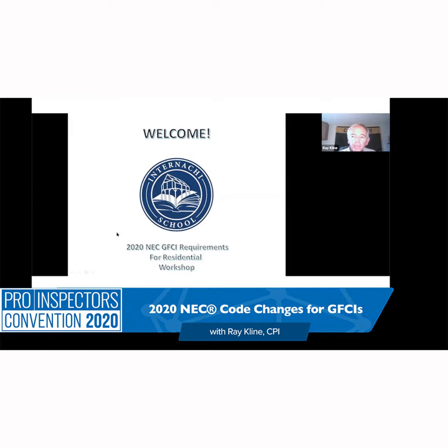It's no longer a judgment call whether or not the basement is unfinished. Now, any and all receptacles in dwelling unit basements are required to have GFCI protection. So that means everything in the basement, regardless of the state of the finishing.